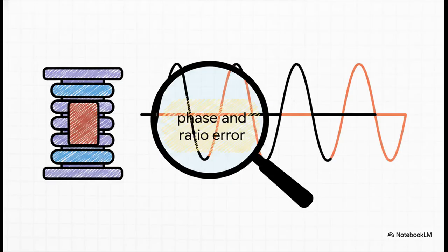And we shouldn't forget about voltage transformers either. VTs have parallel problems. The excitation current drawn by the VT's own magnetic core introduces these small ratio and phase errors between the actual system voltage and what the relay measures. This is exactly why strict accuracy classes exist for both CTs and VTs. You have to ensure the relay gets a mathematically dependable picture of the grid's health.